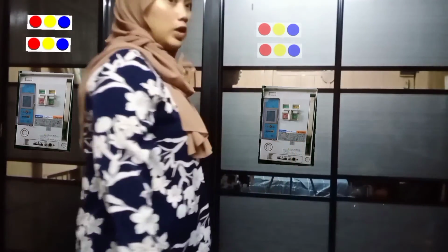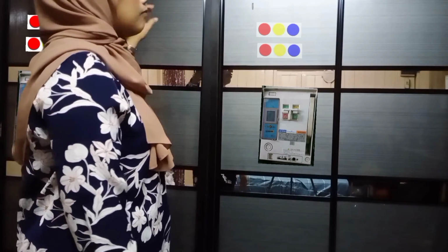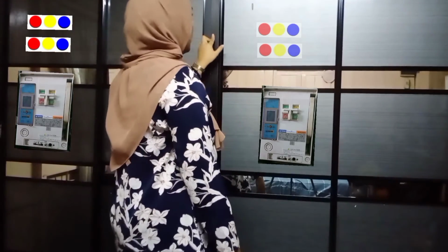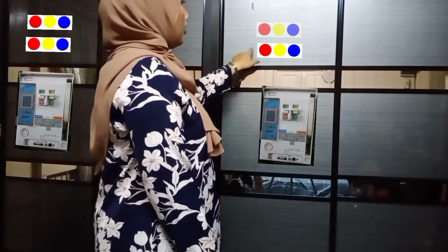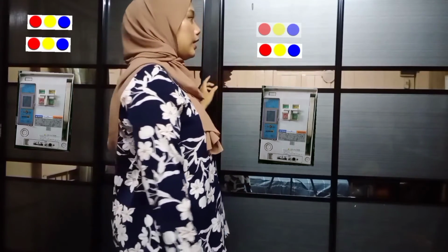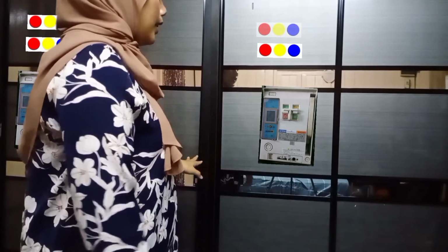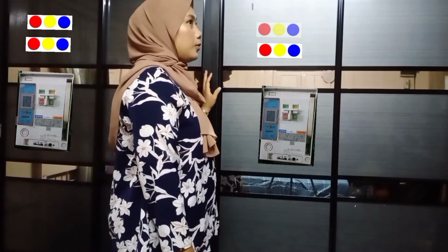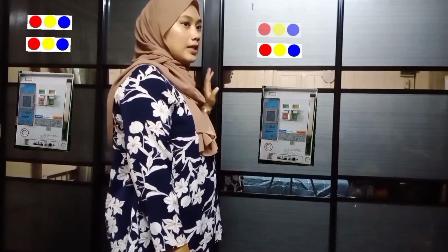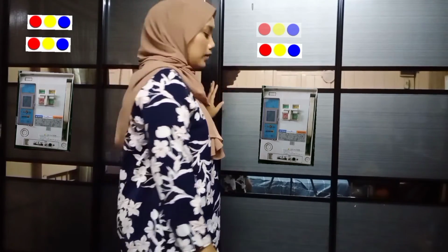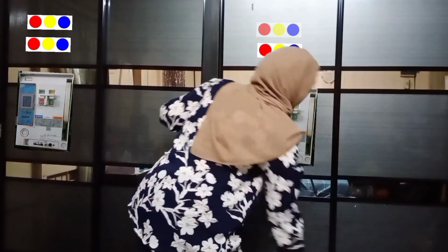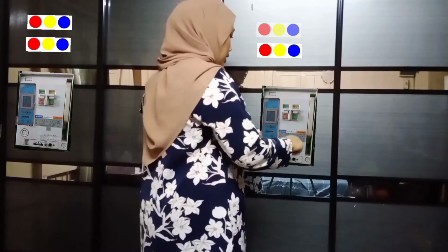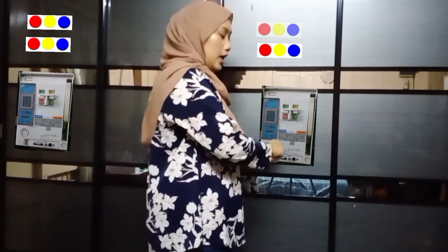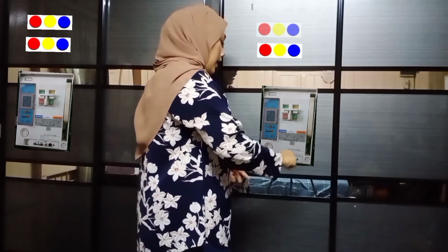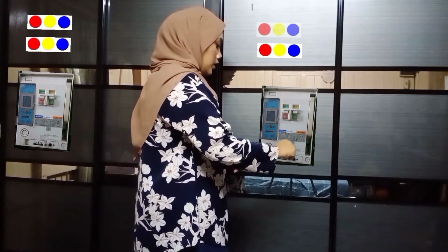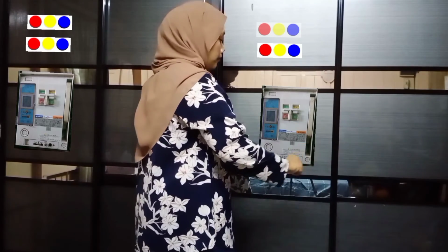First, we switch on the main supply for MSB2. You can see the indicator light is on. Then we need to connect the ACB into the busbar by inserting the charge handle into the slot and turning it clockwise until the isolated position changes into the connect position.